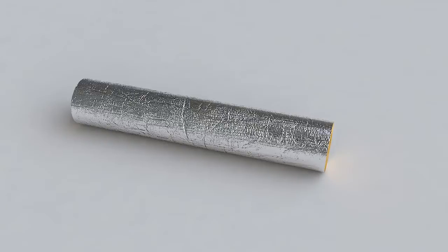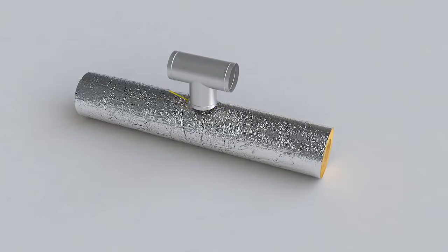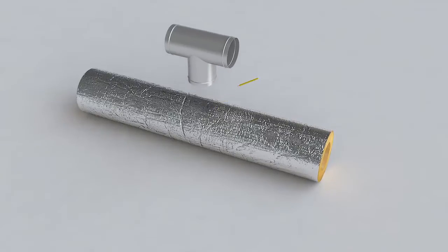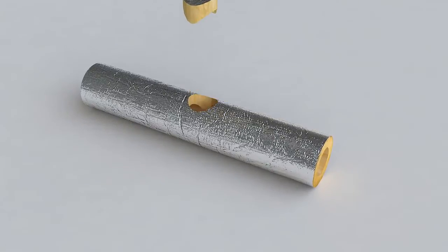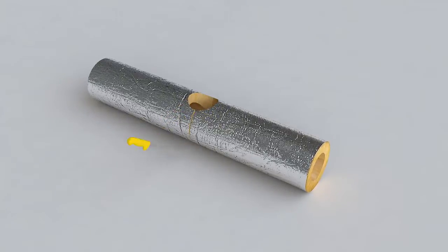Insulating a T branch is just as easy as insulating the angle sections. For a T branch, a circle the size of the projecting branch section is first drawn on the insulation and then cut and removed. The product is cut into two pieces at the center of the hole.